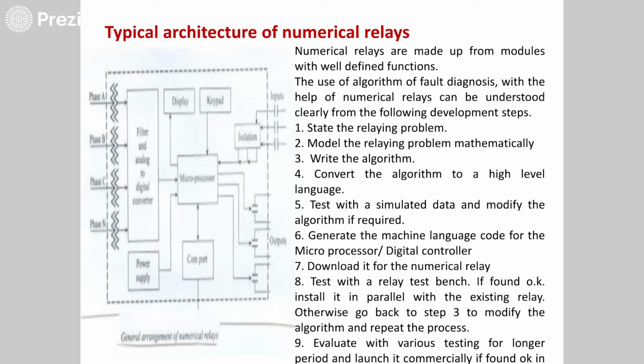Okay, and then to accommodate this large number of input signals, the sampled and held values are passed to the ADC through a multiplexer. So you are going to have a multiplexer as well. Then the microcontroller controls the sample and hold circuit. The instantaneous values of digital signals from the ADC are given to the processor. That means your ADC processes the signal, and the signals are fed to the microprocessor. How is it being fed? It is fed through an input port.